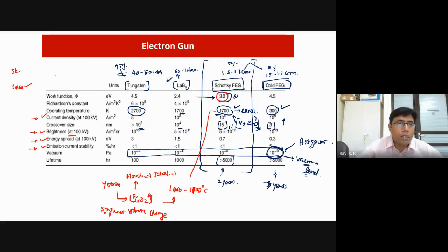Suppose you have a polymeric sample, you may get a very good image at 5 kV, but the same 5 kV may not be good for a metallic or ceramic sample, though again it differs. Sometimes for a metallic sample you may get a good result at 25 kV. But for another sample which is hygroscopic in nature, you have to come down from 25 kV to 5 kV or 10 kV. All those parts we'll discuss in the class, and whatever is possible, also in the lab class.